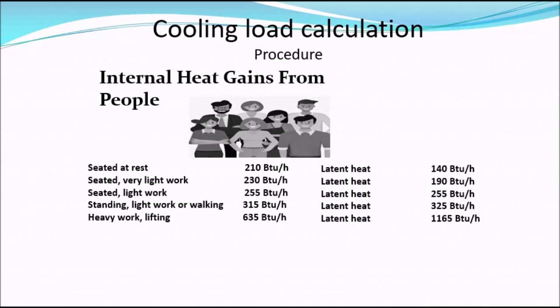The latent heat increases dramatically because of greater perspiration required to maintain body temperature. The amount of sensible and latent heat released by the body varies with age, physical size, gender, type of clothing, and level of physical activity. Based on the occupancy heat gain equivalency table, seated at rest is 210 BTU/hr with a latent heat of 140 BTU/hr.